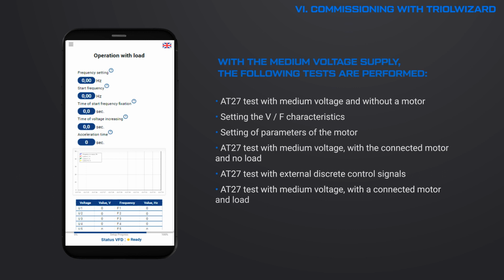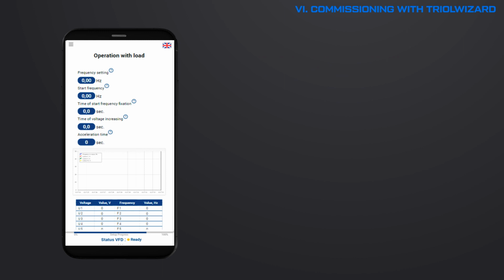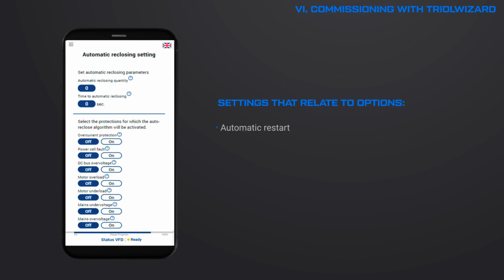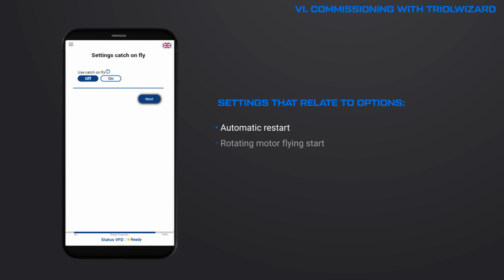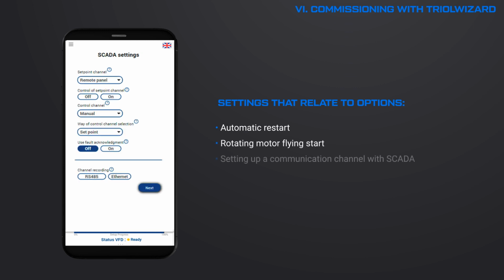In some cases, it is necessary to configure additional AT27 capabilities. For this, the Triol Wizard provides settings that relate to options: automatic restart, rotating motor flying start, setting up a communication channel with SCADA.